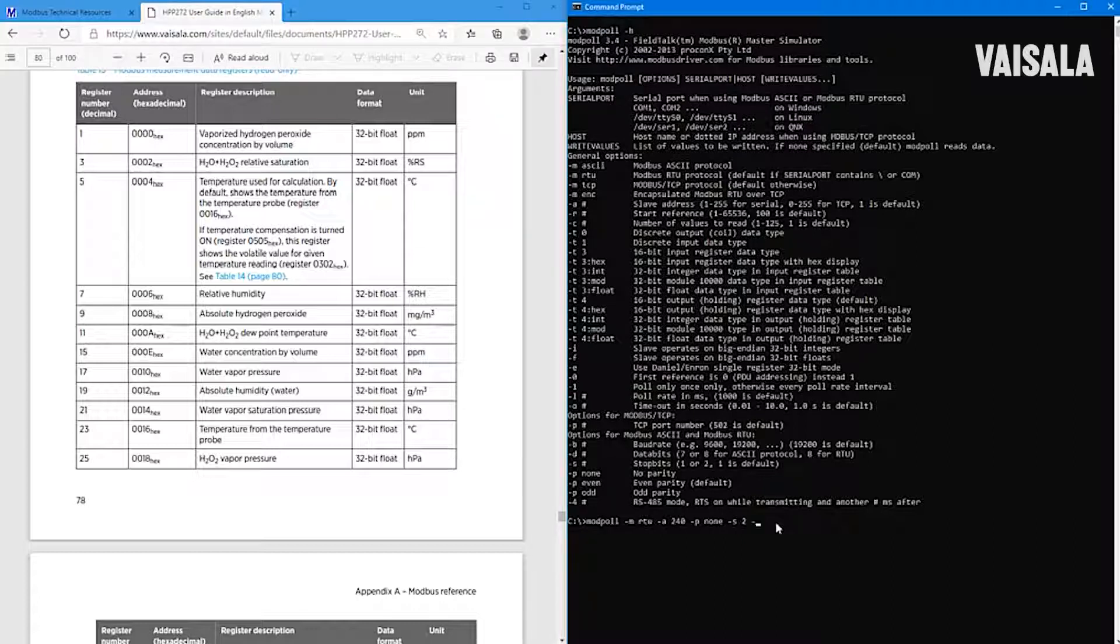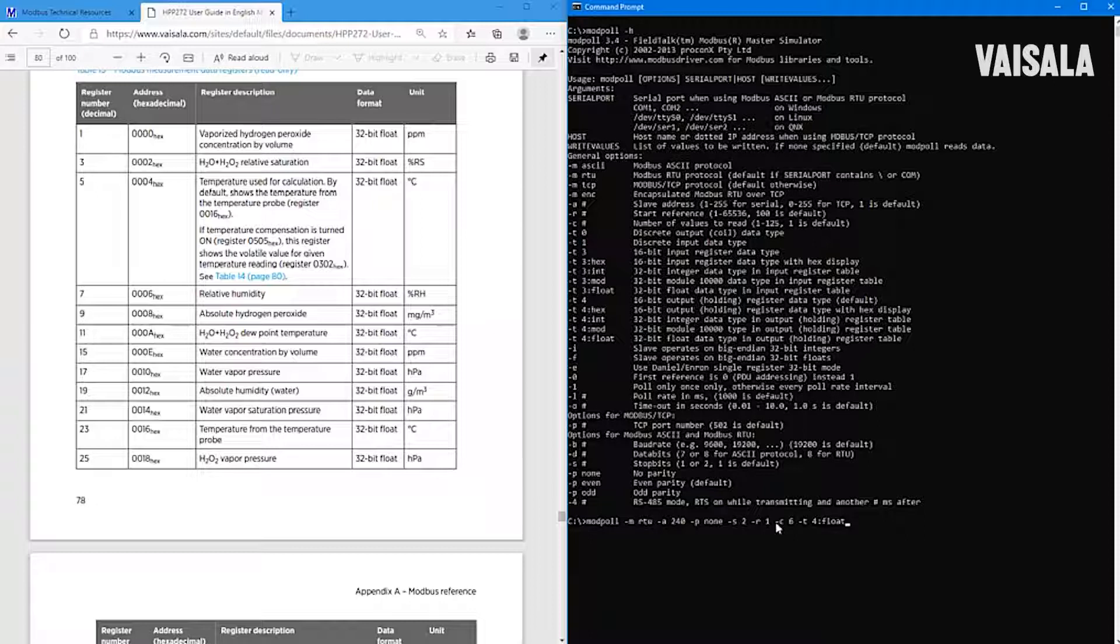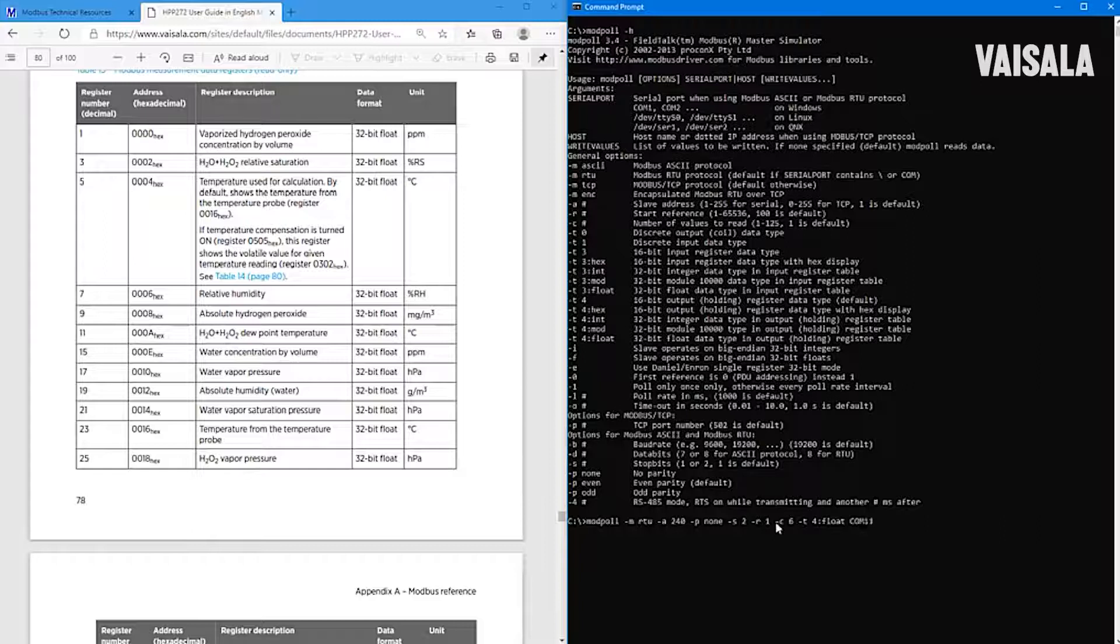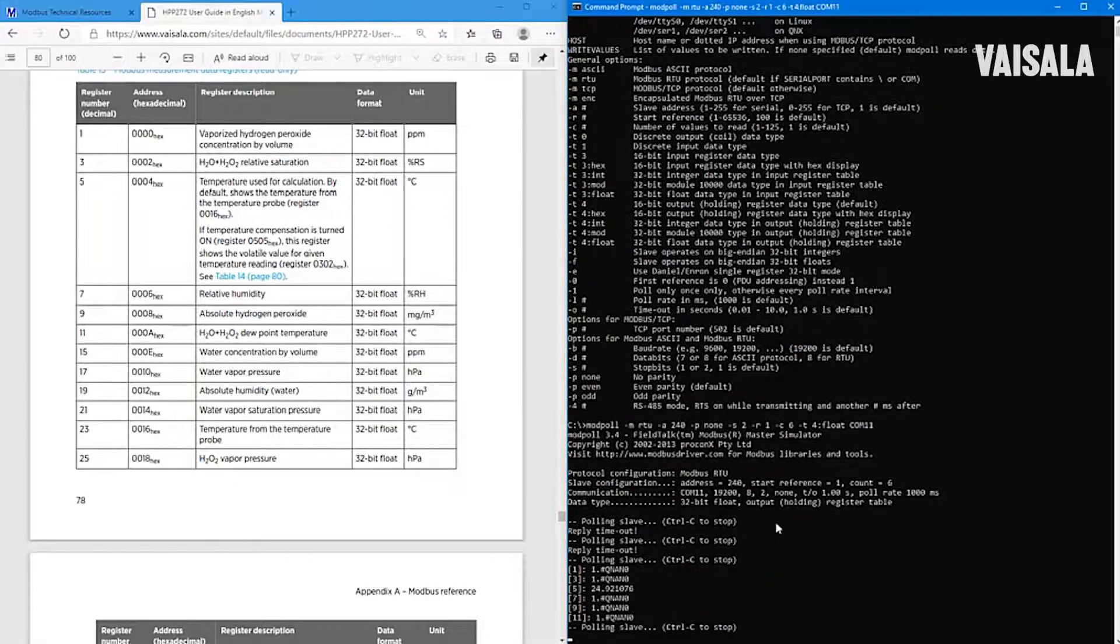So let's read six different values starting from register 1. Sorry, a typo here. And we will read six values. And these are floating point numbers, so let's use t 4:float, meaning that we are now reading holding registers. And then one important thing is to set the right COM port here.